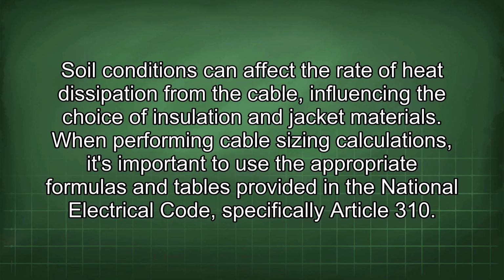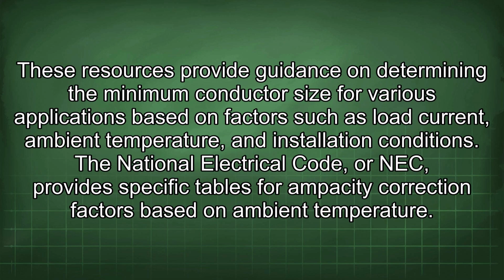When performing cable sizing calculations, it's important to use the appropriate formulas and tables provided in the National Electrical Code, specifically Article 310. These resources provide guidance on determining the minimum conductor size for various applications based on factors such as load current, ambient temperature, and installation conditions.